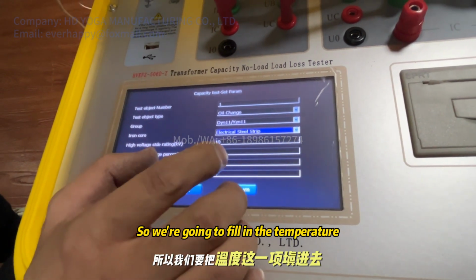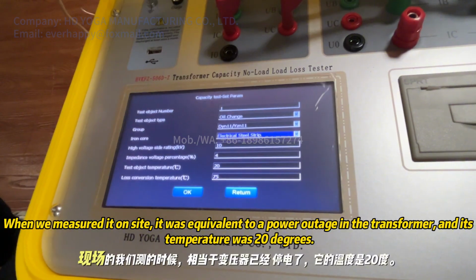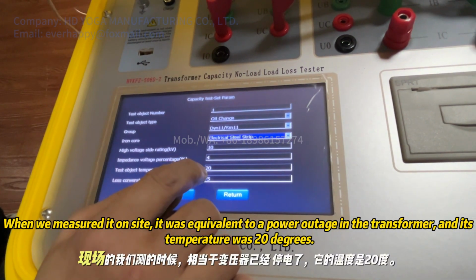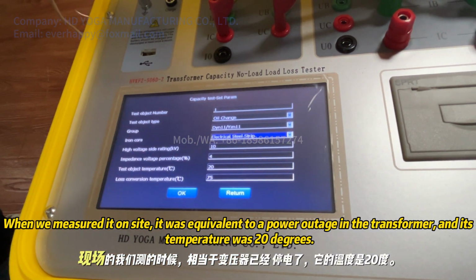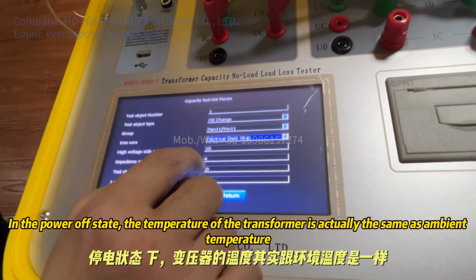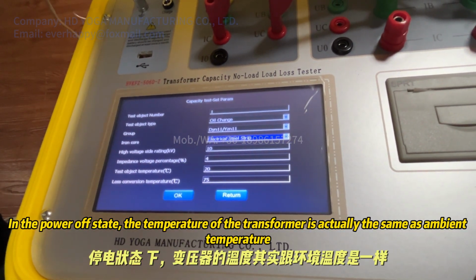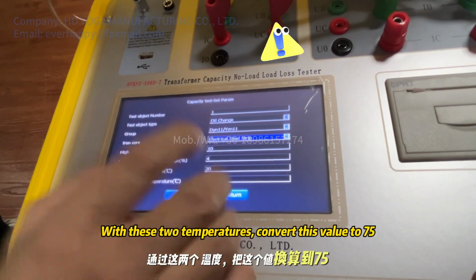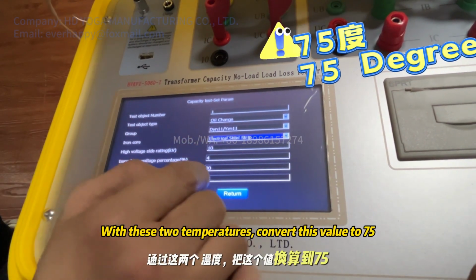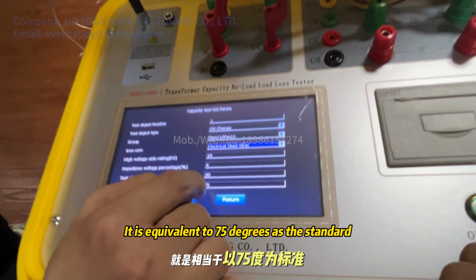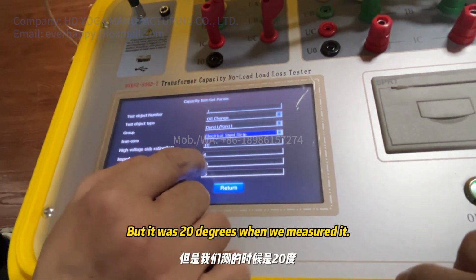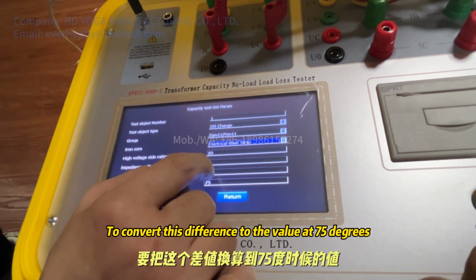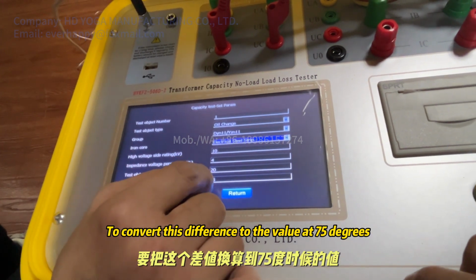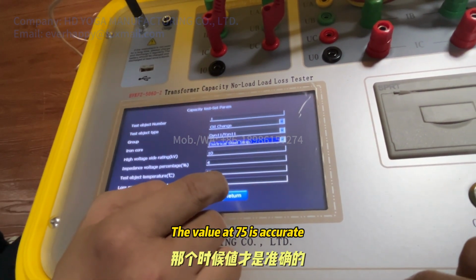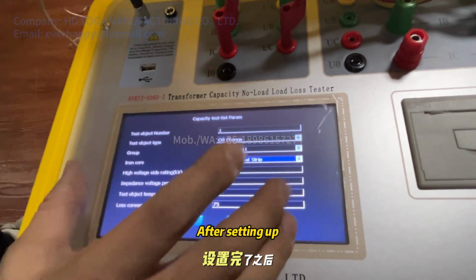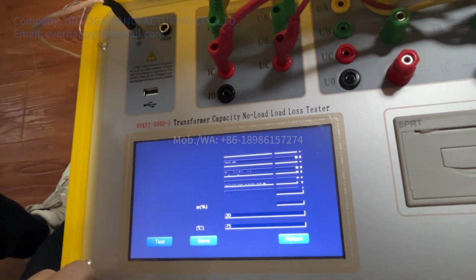So we're going to fill in the temperature. When we measured it on site, it was equivalent to a power outage in the transformer, and its temperature was 20 degrees. In the power off state, the temperature of the transformer is actually the same as ambient temperature. With these two temperatures, convert this value to 75. It is equivalent to 75 degrees as the standard, but it was 20 degrees when we measured it. To convert this difference to the value at 75 degrees, the value at 75 is accurate. After setting up, let's click OK directly.